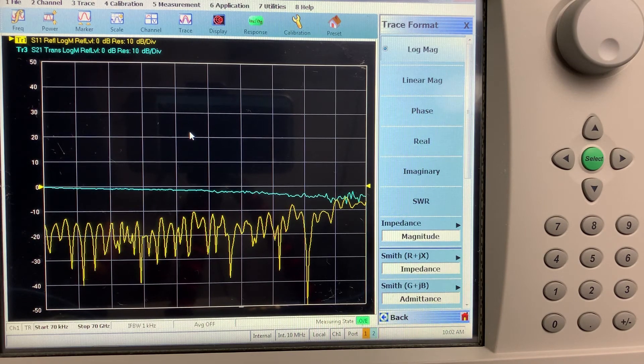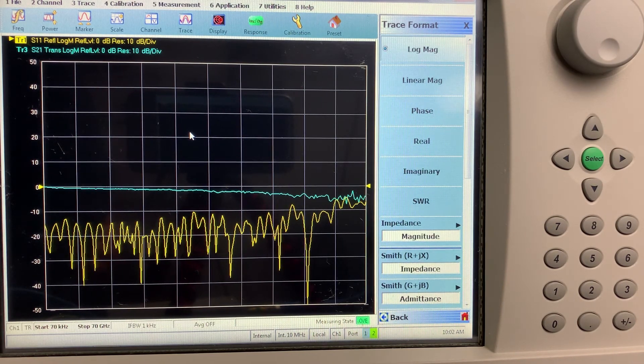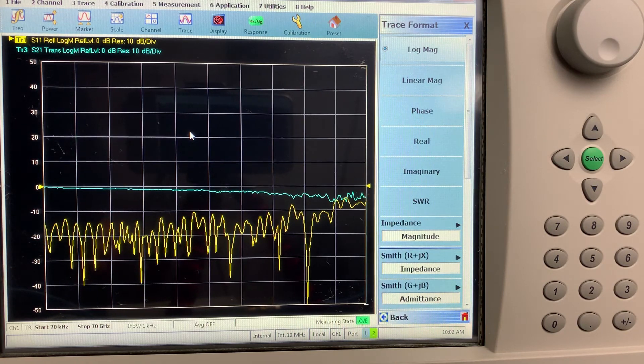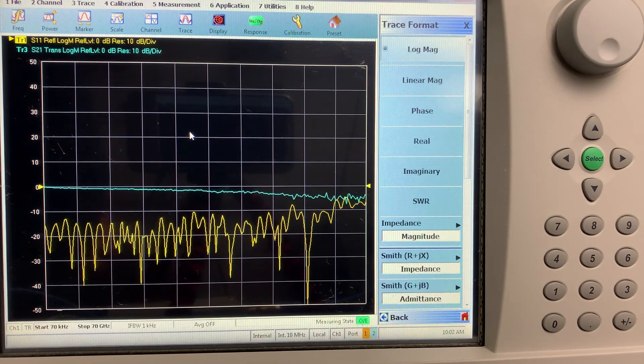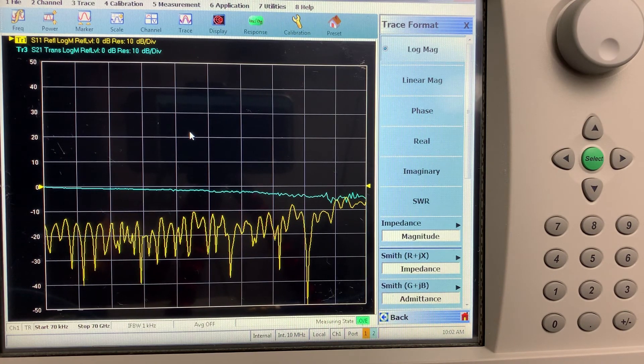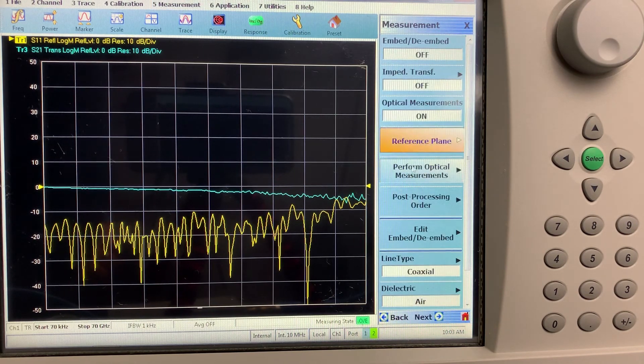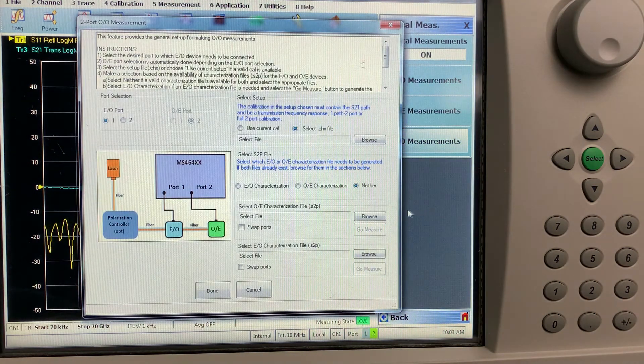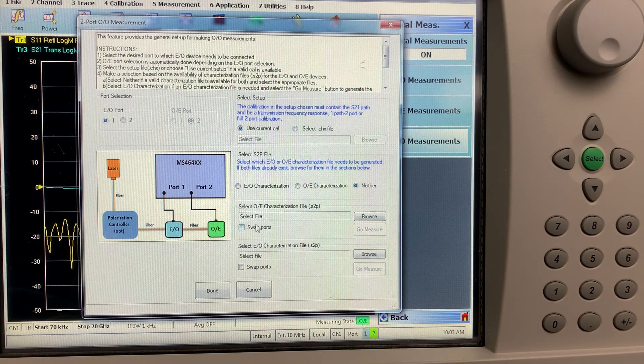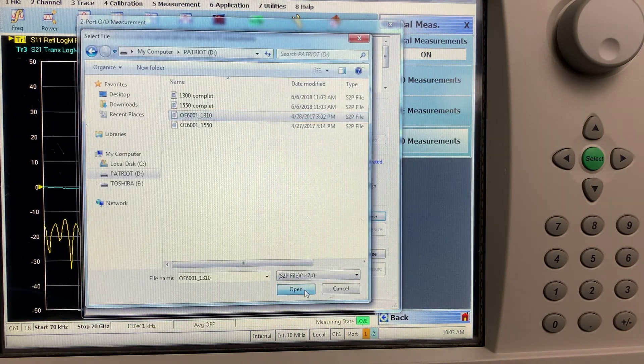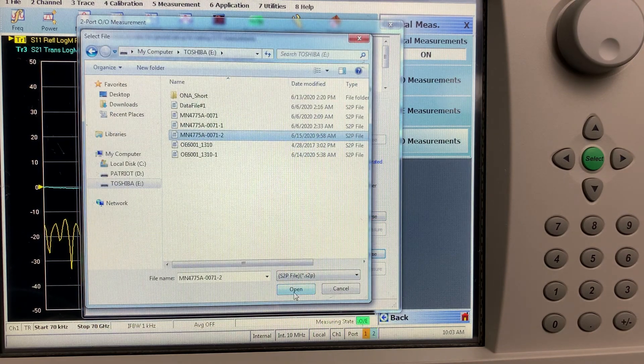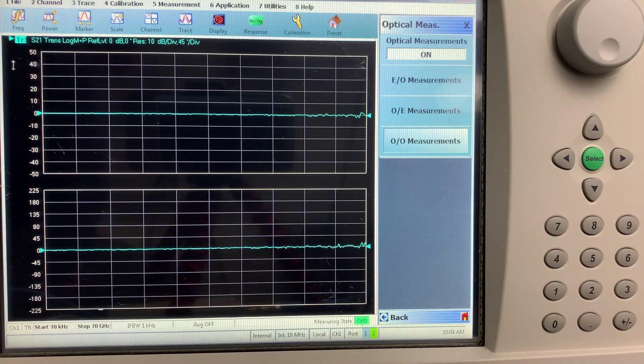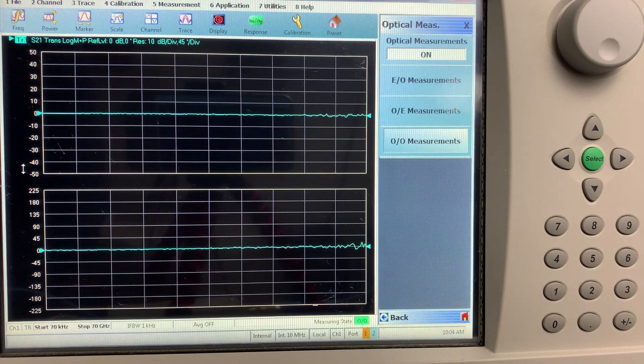And now because we have both O2E S2P files and E2O S2P files, we can de-embed them both and do an O2O measurement of the optical cable between the optical out of the converter and the optical in of the O2E calibration module. And you'll see the measurement of the optical cable is zero.